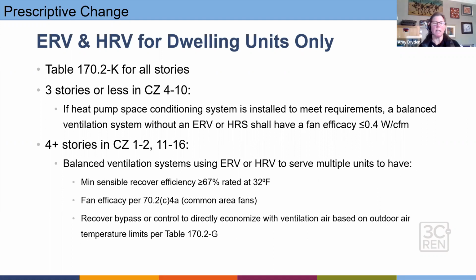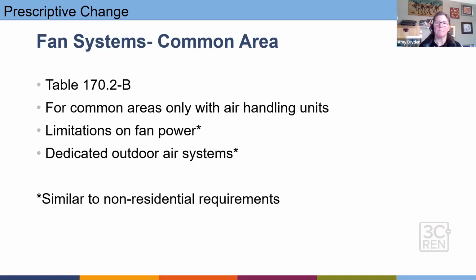So there are minimum recovery efficiency factors you can see there at 67%. We have fan efficacy requirements for these fans, and we have recovery bypass or controls to economize, like it says, economize with ventilation air based on outdoor air temperature limits. And so again, if we're looking at the operation of these types of systems, because they are meeting ASHRAE 62.2, there are additional requirements for efficiency. That's it. Okay.